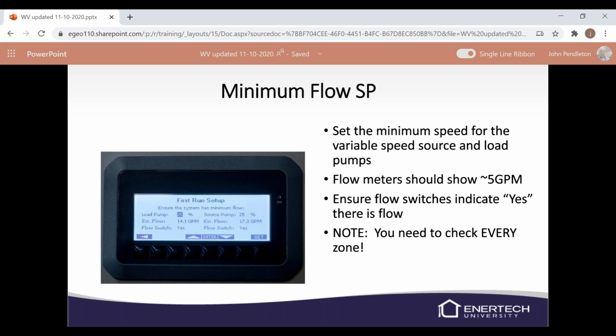We want that pump minimum speed. I don't really care where it's set at. Whatever that minimum pump speed is, it needs to make sure that our flow is above 5 GPM. So if it's 25%, then so be it. I see on the load, it's about 60% is your pump minimum. Somewhere between 45 and 60% is what I normally see. So you can start out whatever it is when it comes up on the screen and see where you're at. It gives you a chance to kind of play around with it.